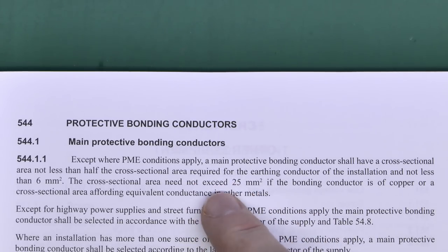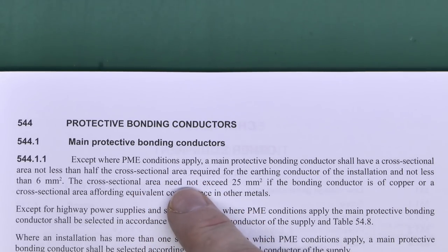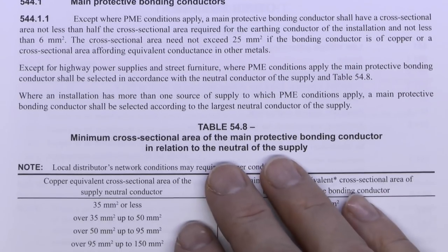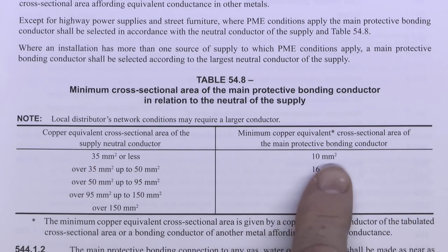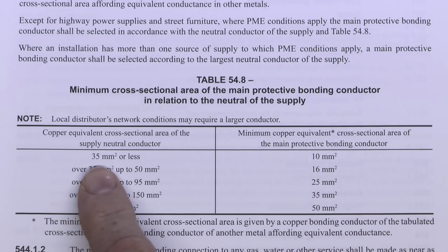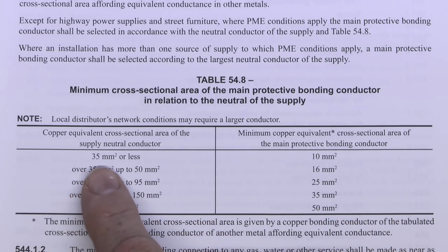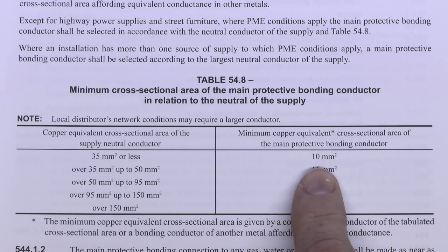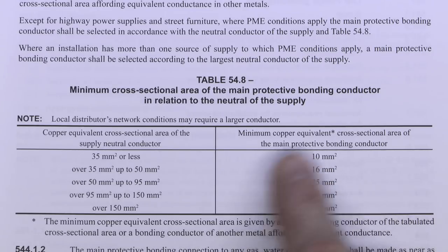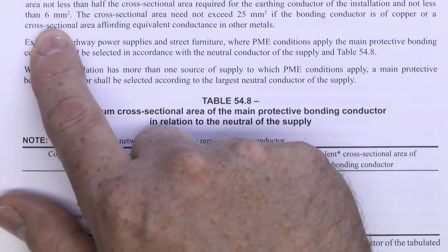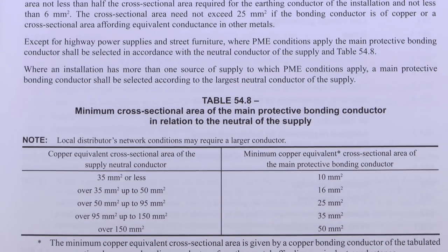This only applies to non-PME supplies, so essentially TNS and TT supplies. In the event of a PME supply, which is generally the TNCS arrangement, you select from a table where the minimum size is 10mm² for supplies up to 35mm² or less — and as the supply size increases the minimum size increases also. For a domestic property it's highly unlikely to have a supply above 35mm², so 10mm² is generally the standard size used. It generally ends up as 10mm² since it's more convenient than buying a separate roll of 6mm².